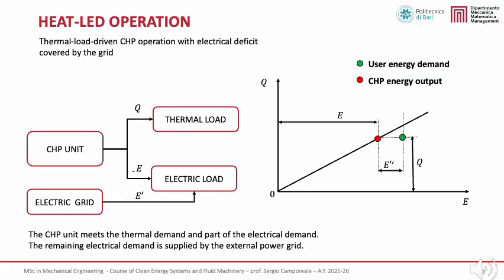In this case, the system is sized according to thermal demand, and the thermal load fixes the operating point of the CHP unit. The corresponding electrical output, E prime, is determined by the CHP characteristic and may be lower than the user's electrical demand. The remaining electrical demand, E double prime, is therefore supplied by the external electricity grid. This configuration typically ensures high heat utilization and is common in applications with a strong and continuous thermal demand.